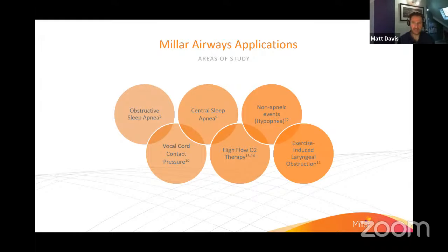Millar technology excels at measuring small pressure changes in low pressure environments. As discussed previously, both ICP and IFP are low pressure applications, along with most airway applications where you would be looking at pressures in the region of, say, -10 to 30 mmHg. All our sensors measure pressure changes by deformation strain.